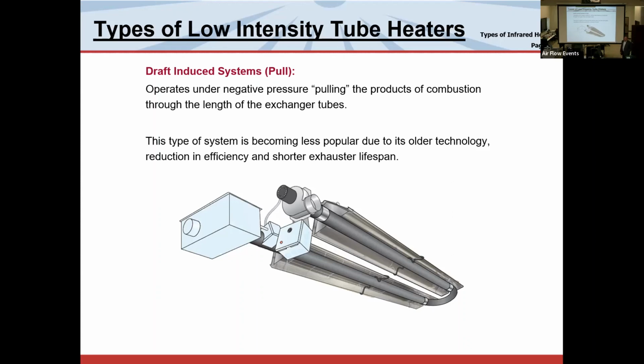The advantage to putting a pump at the end is that you can often put vent lengths double what you could otherwise. Because at this point, you have velocity. You're moving. So if I need to vent 40 feet away from where the heater is, putting that type of system in makes sense. What is also unique about this picture? What configuration is that heater in? A U shape. That means that that hot tube where the flame is impinging is directly opposite the cold tube where the baffle is. Right? If you're heating for comfort, you're trying to heat picnic areas or golf driving ranges or outdoor patios, go to a U-tube, because the U-tube will keep you out of trouble and it's going to be the most comfortable for people.